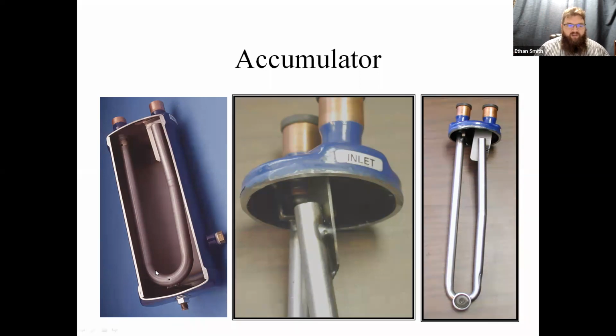If your oil level is above a couple inches above the bottom of the accumulator, you'll likely have a plugged screen in the accumulator, and you should be changing that accumulator along with the compressor. This unfortunately happens more than I care to admit. I unfortunately only get involved with it after they've changed the compressor multiple times.